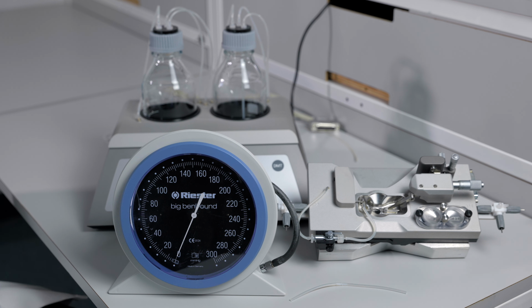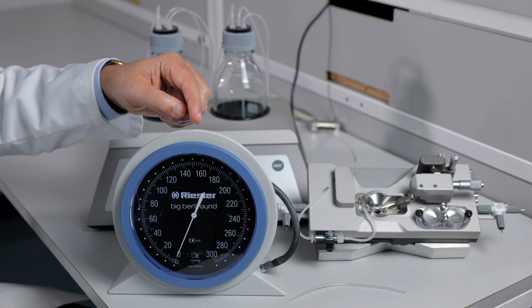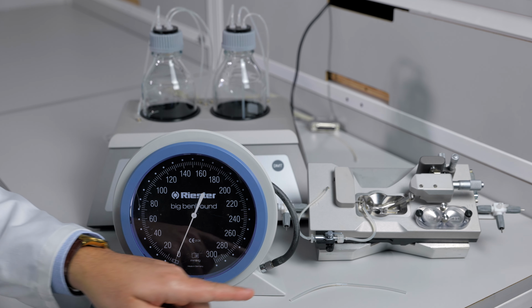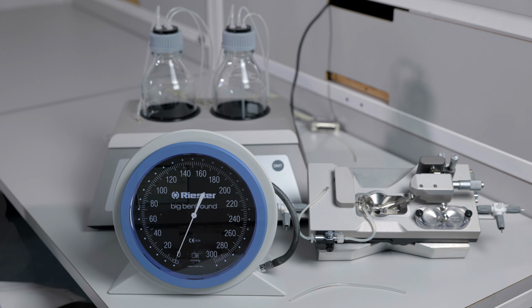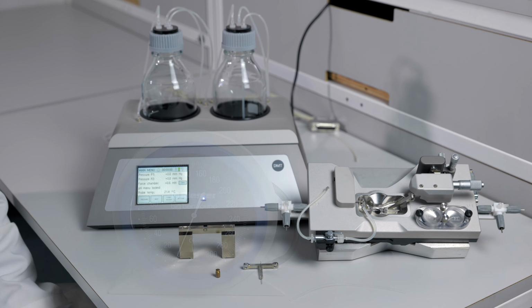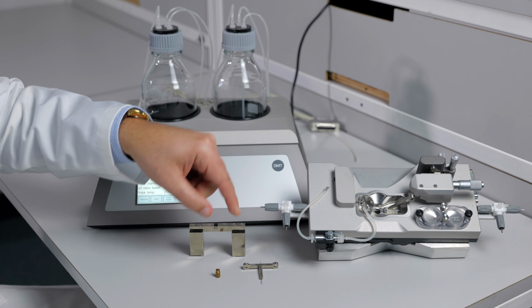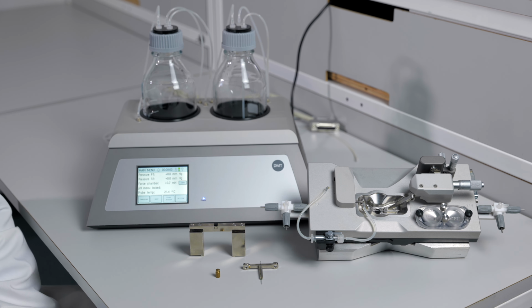This video will show the calibration process for the force and the pressure transducers on the 112 pp pressure myograph system. We will start with the pressure calibration and then do the force calibration. In order to perform the pressure calibration, you will need the Big Ben pressure manometer and the calibration shunt, which came with your system. The force calibration requires the calibration kit that came with this particular system. This includes the calibration bridge, which is specific for the pressure myographs, the T-balance, and the 2-gram weight.